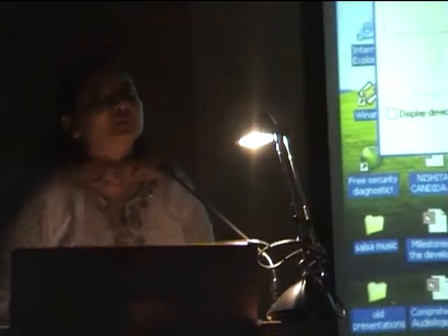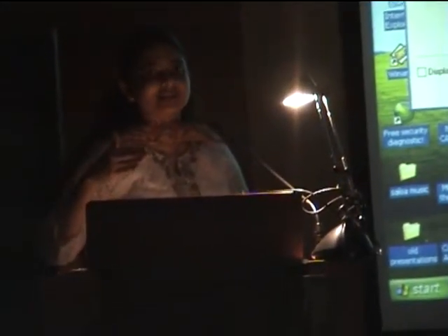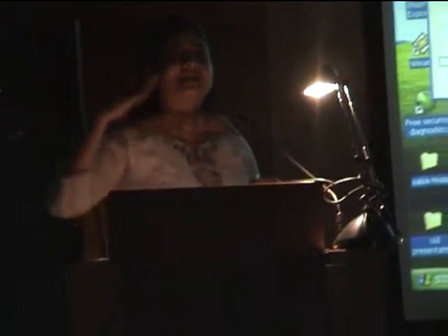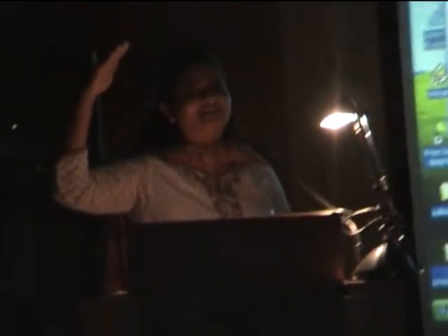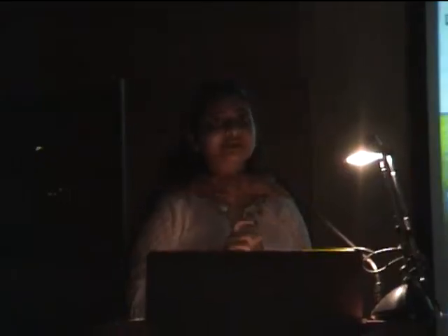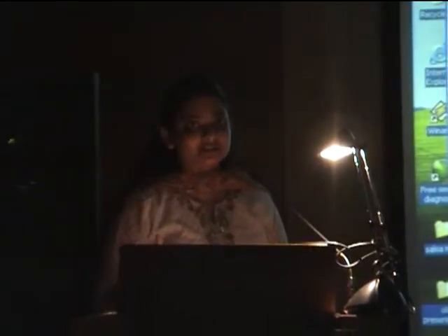Tolerate sounds which are much above this comfortable level. No, see the thing is, we say that we don't want to over amplify the electrical current. When we talk about the acoustic dynamic range, we have a far wide range which starts at the threshold, which in a normal person is around anywhere between 0 to 10, and the uncomfortable level comes around 110, 120. That is such a wide range, which is not possible here, because we are dealing with electrical current and you cannot have the same kind of dynamic range here.